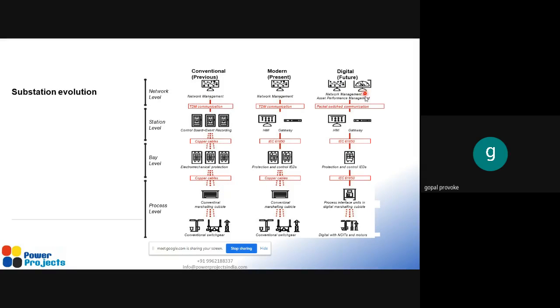When we go to the digital substation, there are very significant and important changes in the substation equipments also. Comparatively, there is not much difference between the conventional substation and the modern, present day substation. But in the future, we are going to use non-conventional instrument transformers instead of the present day CT and VT, and this will occupy very less area. These non-conventional instrument transformers, or optical current transformers and optical voltage transformers, are like sensors, and these sensors will occupy very little area compared to the present day substation.